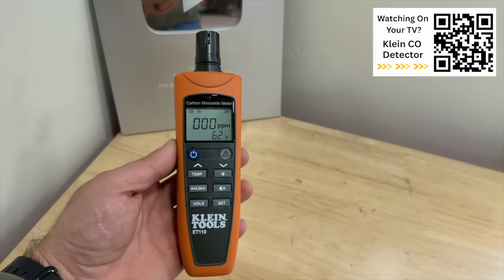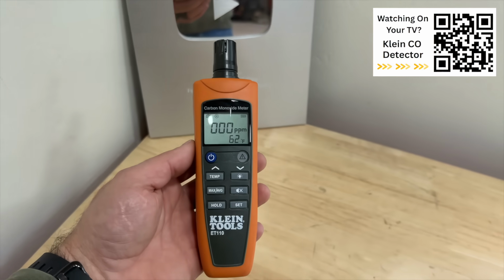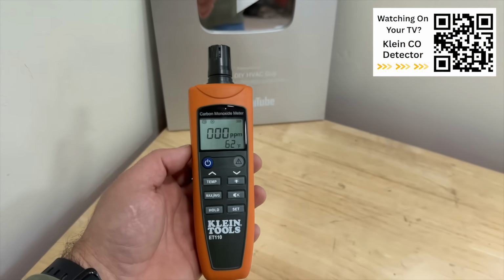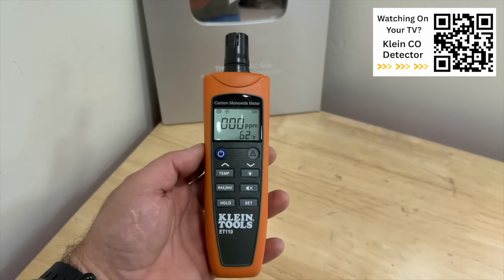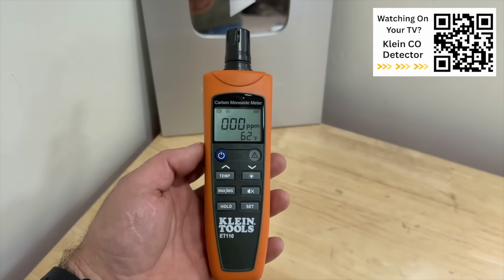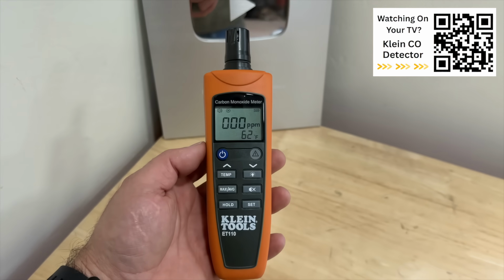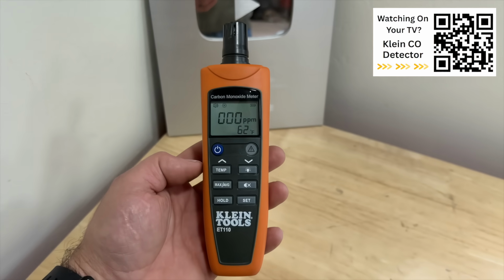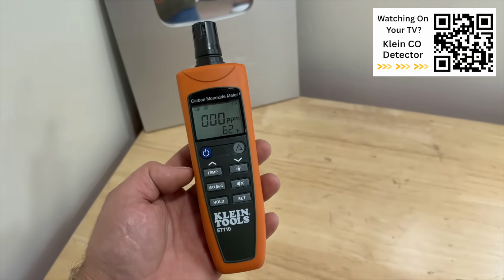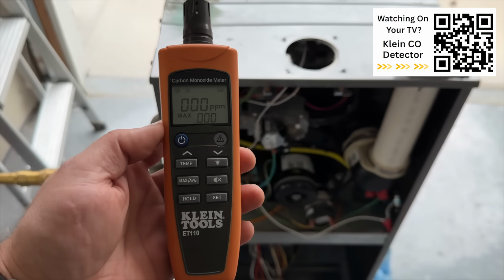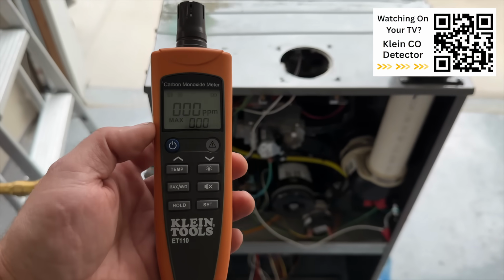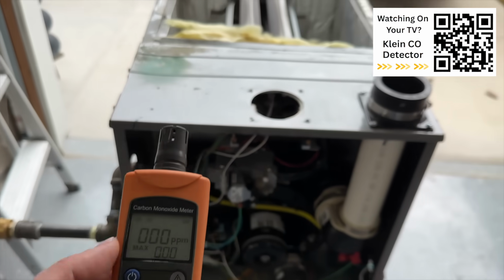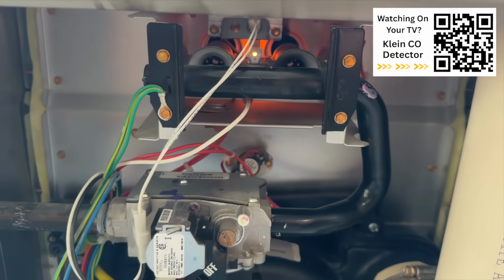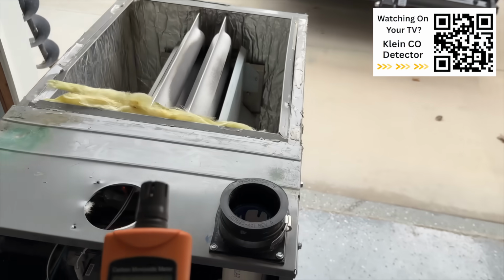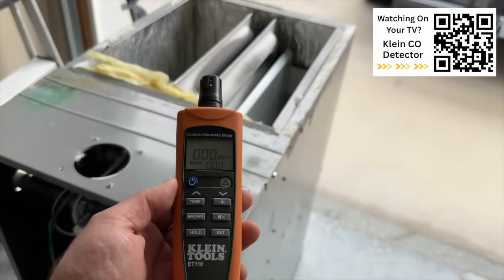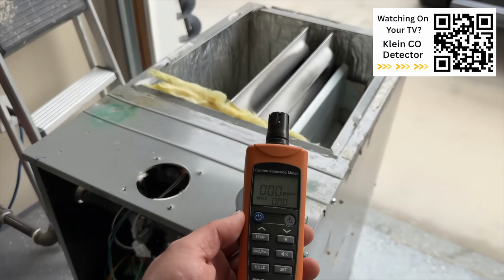You can get cheaper ones, but for something as critical as carbon monoxide, I really would emphasize getting one that is nicer, like this Klein device right here. So I'm going to demonstrate how this works and what you can expect if you get a carbon monoxide detector like this one. All right, so we've got our carbon monoxide detector here. It does a little countdown to calibrate the sensor up top. Our hot surface igniter is on right here. And I just want to demonstrate how you will immediately sense carbon monoxide.